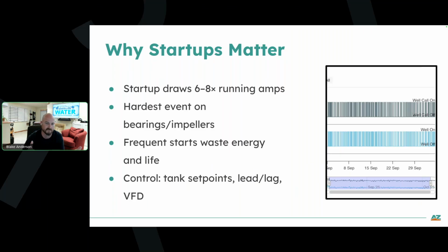If the building had smelled different or it felt hot in there, I could have told you that sort of stuff that would have indicated booster health. But your starts and stops, if you don't have a mechanism to track it, gets pretty difficult. And so, especially for operators that are running smaller systems, I really recommend looking into SCADA if you don't have it currently.